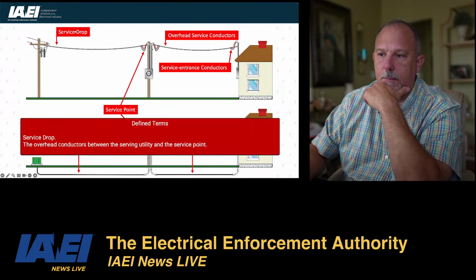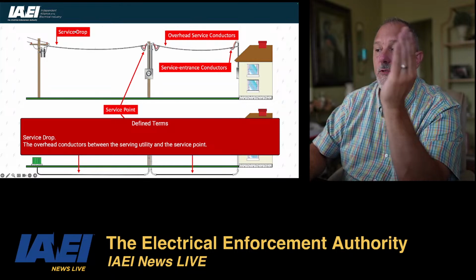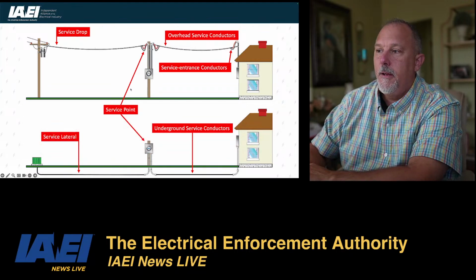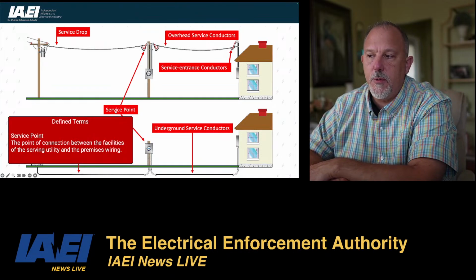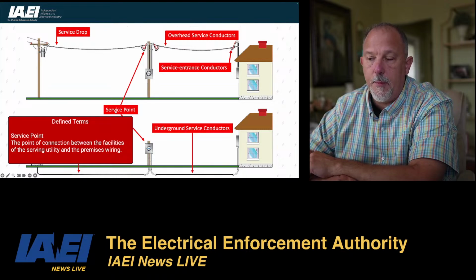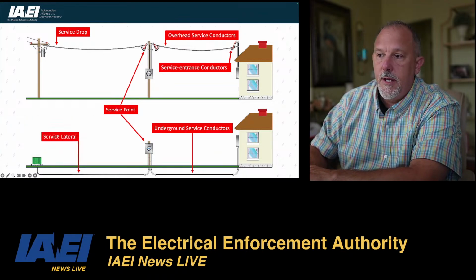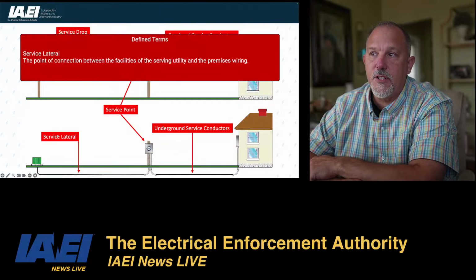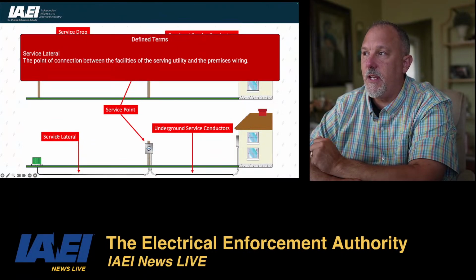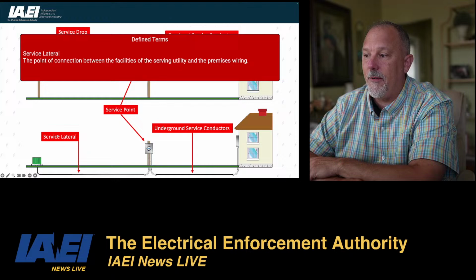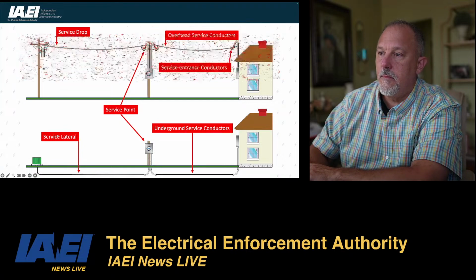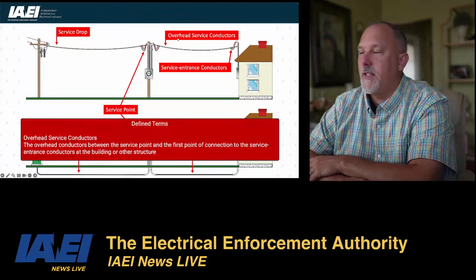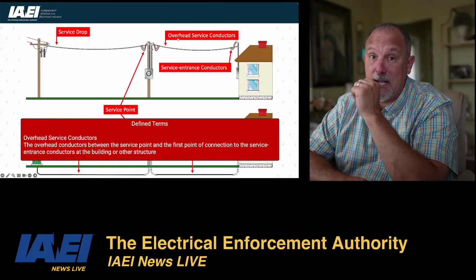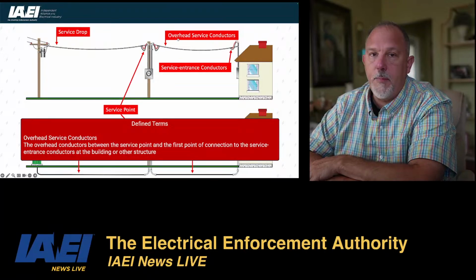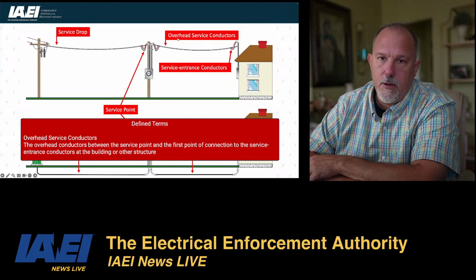There's your service drop, the overhead conductors between the serving utility and the service point. This is your service point, the point of connection between the facilities of the serving utility and the premises wiring. This is your service lateral. The lateral is the point of connection between the facilities of serving utility and the premises wiring. These are your overhead service conductors. None of these locations can you tap into for PV or any alternative energy solution.